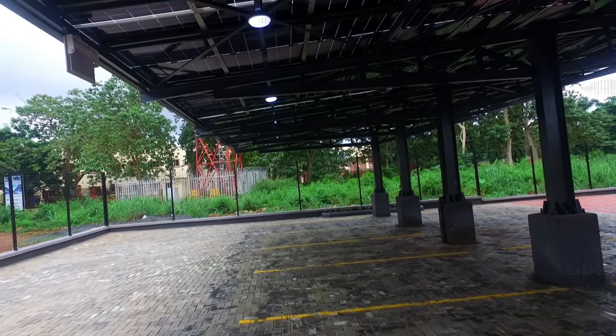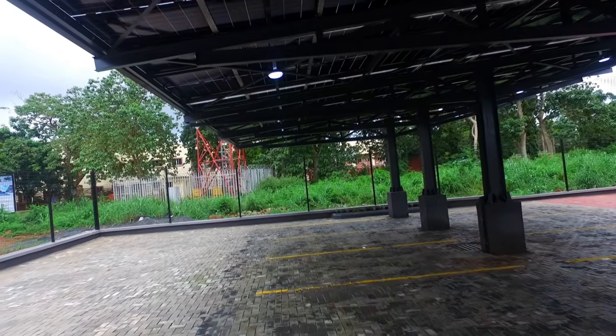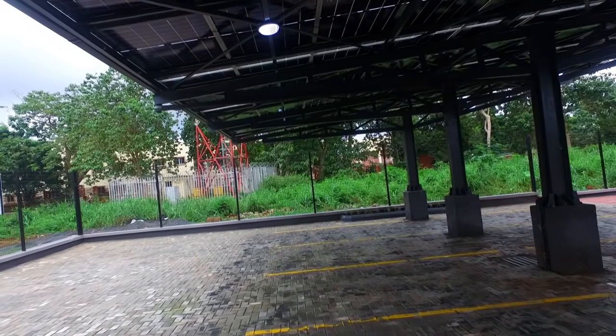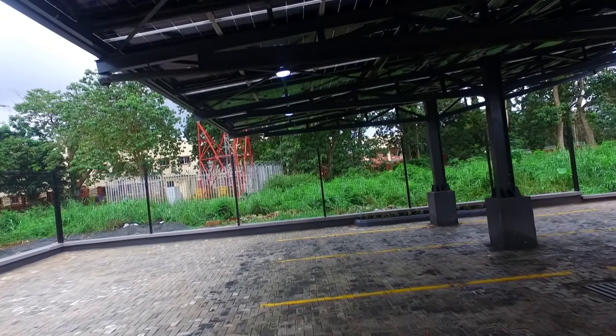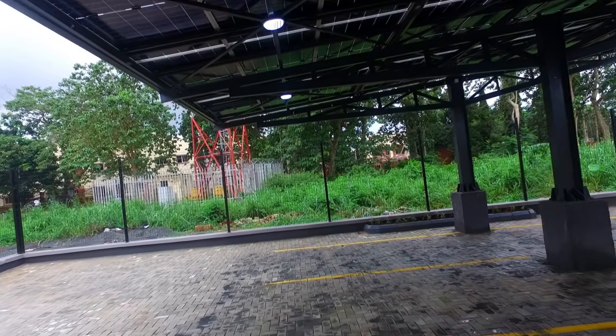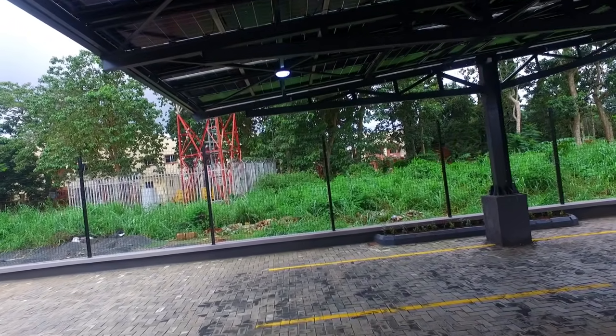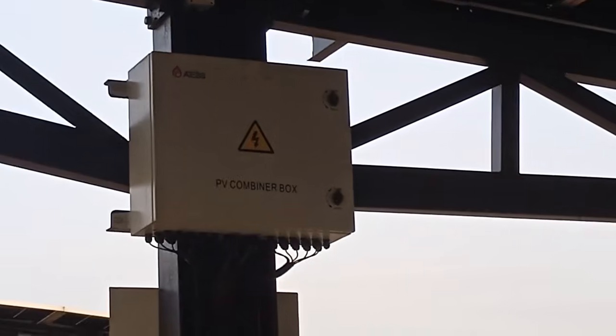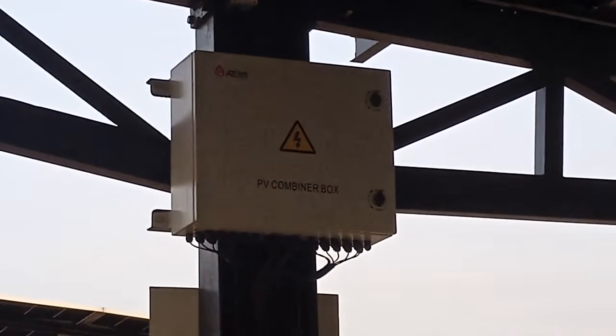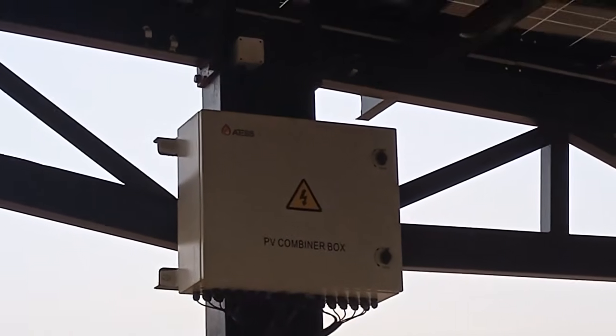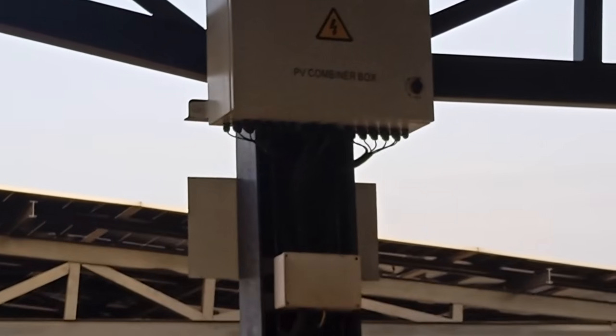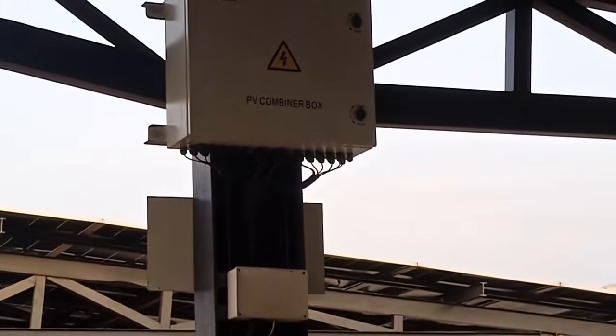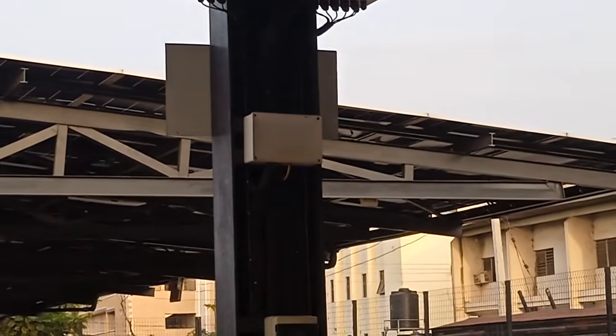When you hear bifacial solar panels, these are solar panels that can generate electricity on both the front and the rear side of the panel. And the rear side of the panels, at optimal condition, can produce about 30% extra energy. Now we have the PV combiner box, where the strings of panels are connected in parallel. Like I said earlier, we have 7 strings of panels connected in parallel in this PV combiner box. Then the output goes straight to the hybrid inverter.